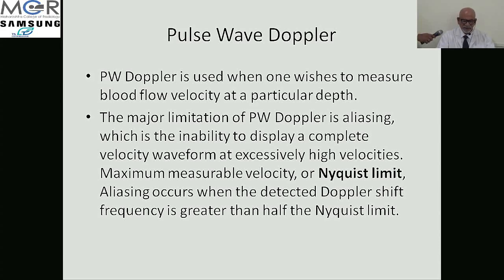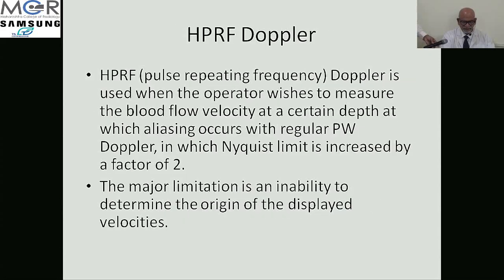The major limitation of PW Doppler is aliasing, which is the inability to display a complete velocity waveform at excessively high velocities. Now the Nyquist limit is the maximum measurable velocity of that particular probe. Aliasing occurs when the detected Doppler shift frequency is greater than half the PRF, the Nyquist limit. Okay, so this is a limiting factor. It can tell you the location, but it cannot tell you the velocities. This is the problem with pulse wave Doppler technology.